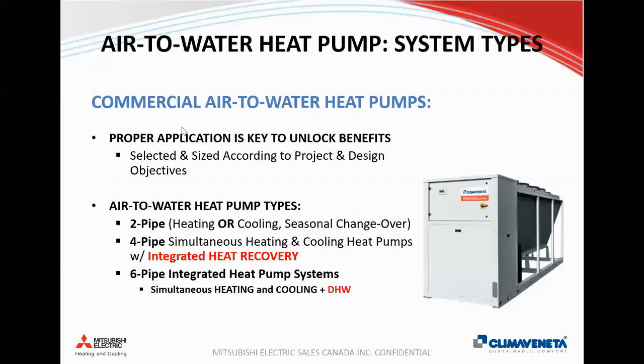Commercial air to water heat pumps are a little bit different, and basically the main takeaway that I want people to take away from this presentation and commercial heat pumps is, there's a reason why we call it an applied product. We have to think a little bit differently about how we design systems to get the best value for that equipment that we're putting into the building. So really designing it in parallel with your project and design requirements, fit the project around the heat pump if you're trying to get a low carbon solution, instead of the other way around of having a building say, okay, now how do I fit this heat pump into the project to get rid of carbon?